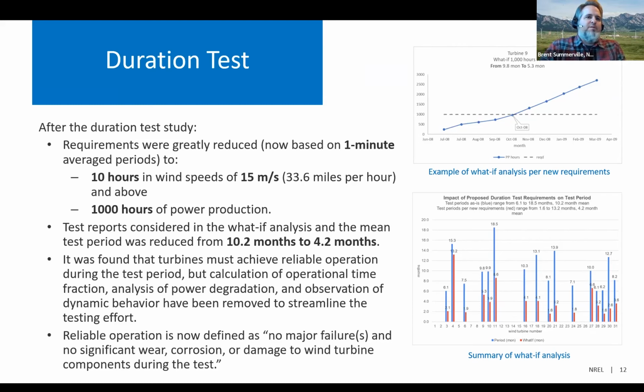And I guess I'm sort of missing the used-to-be numbers, but it used to be 2,500 hours of power production, and then various levels of hours above wind speeds, including very high 1.8 times V average, or even 2.2 times the V average based on whatever IEC class was chosen. So this is a pretty dramatic reduction. So somewhere in between getting rid of the duration test and keeping it as it is lies a sweet spot, which we hope we got close to.